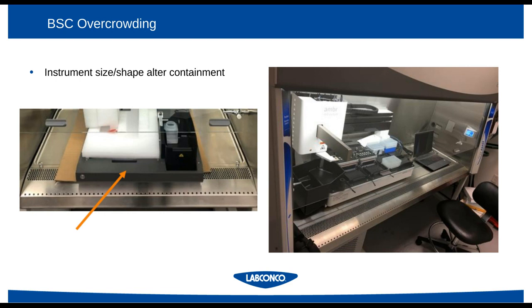On the right, this is a bioreactor from Sartorius, and this instrument is actually capable of performing inside the biosafety cabinet and can contain, but we only know that with most instruments after some thorough testing, things like smoke airflow studies and biological containment challenges. So it is key and really important to look at the instruments that you might be using and consult with the manufacturer of your biosafety cabinet before progressing.